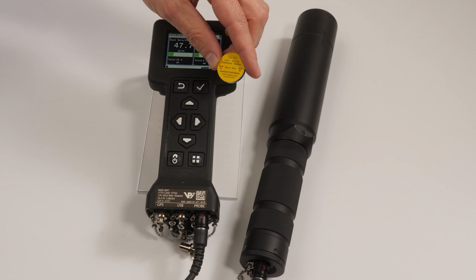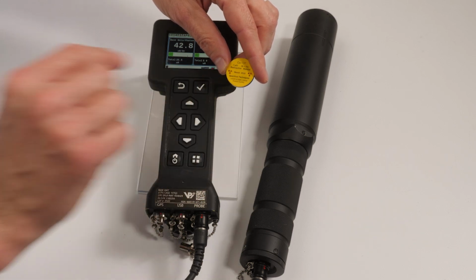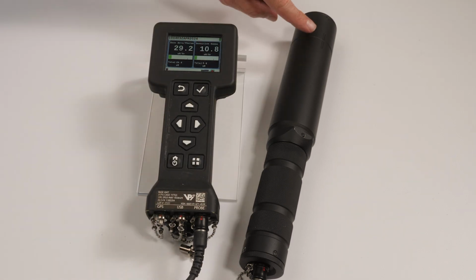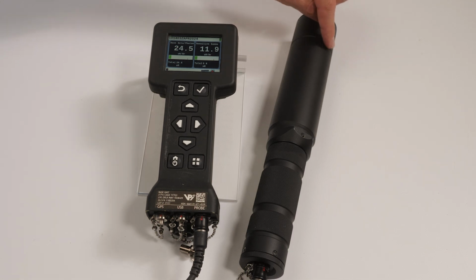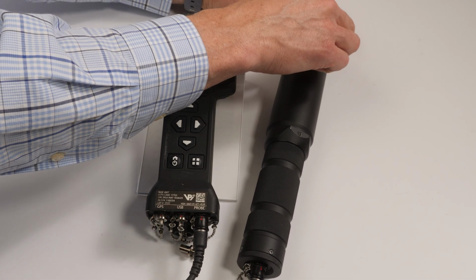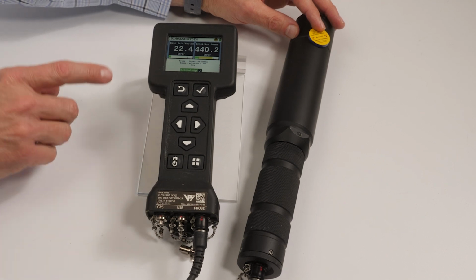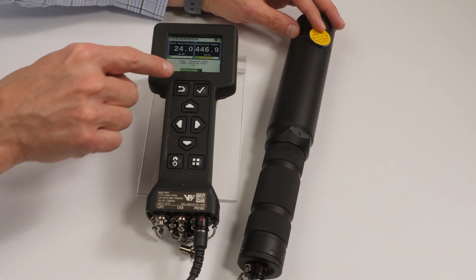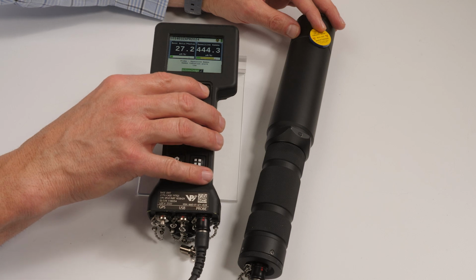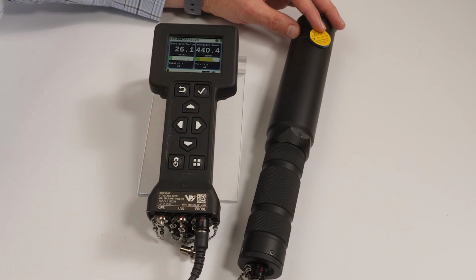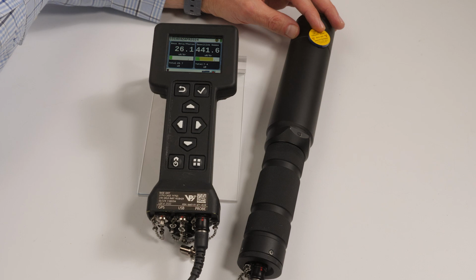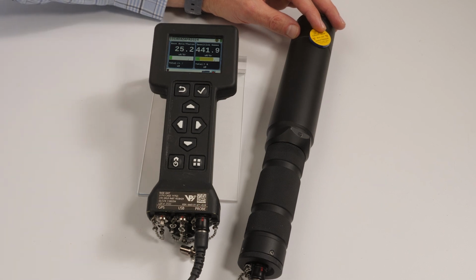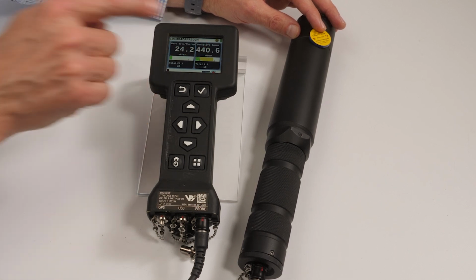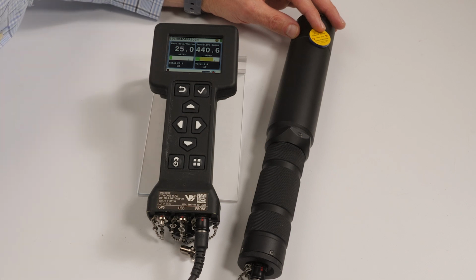Locate the 1 microcurie cesium-137 check source, ensuring you are using one that is not over 30 years of age. Place the check source in direct contact with the sensitive gamma probe's detector center mark, with the label facing away from the probe. If the alarm thresholds are set at a level that causes an alarm, acknowledge the alarm by pressing the Enter key. Hold the check source in place for at least 30 seconds, allowing the radiation reading to settle. Verify that the radiation reading value falls within the range of 150 to 775 microR per hour.